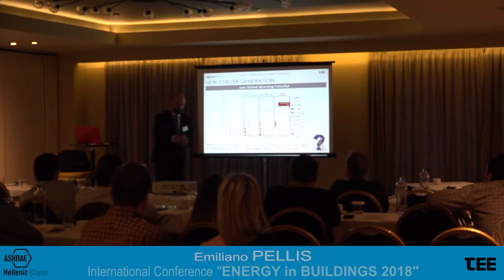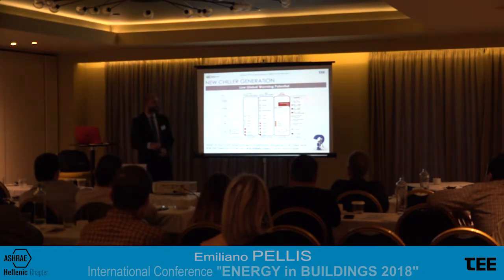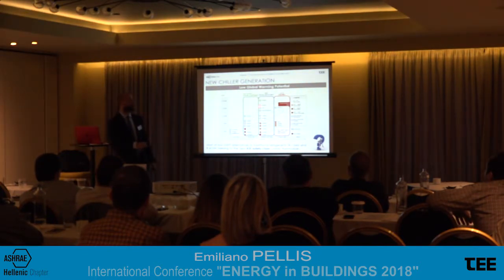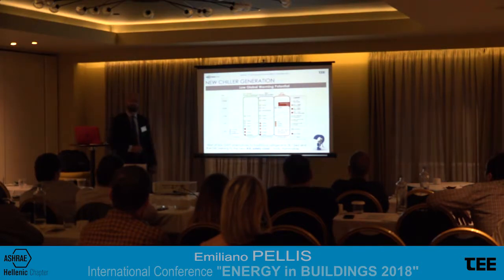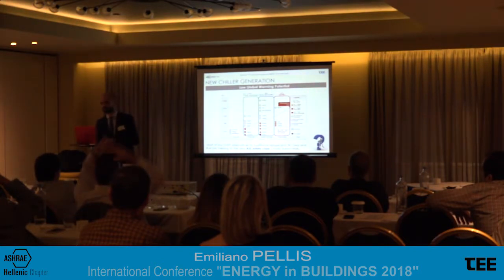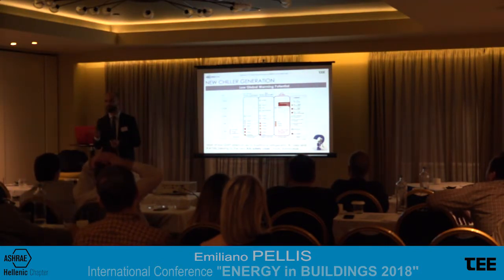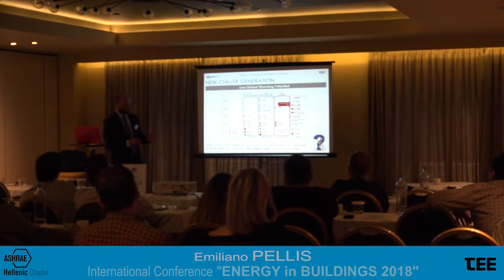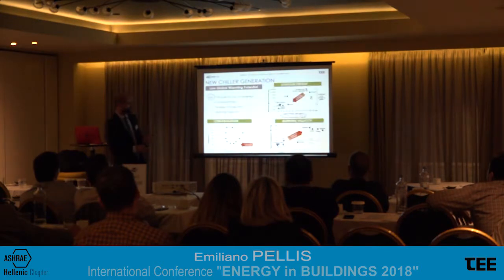If you see in details this chart, you see in particular this red line, which is the flammability line. What is above the red line is not flammable. What is below is flammable. The message is, if we want to move to a very good alternative solution with low GWP, we have to accept some compromise in terms of flammability. You know, 134A and 410A are A1 class, so not flammable, according to the ASHRAE classification. We have to accept this compromise. Why? Oh, sorry, excuse me. Why?